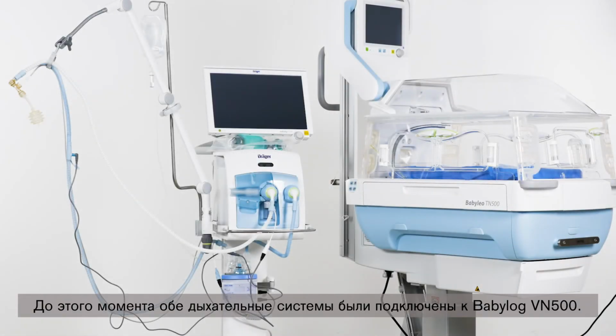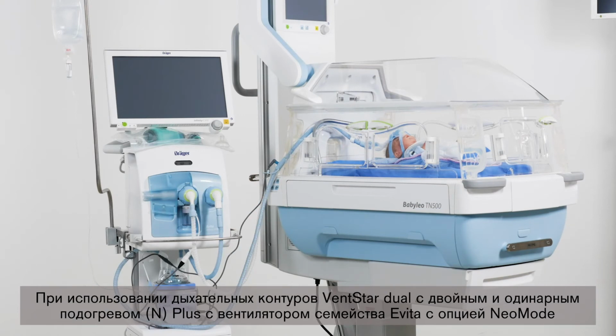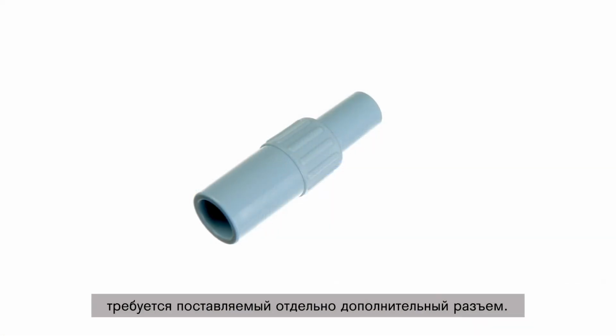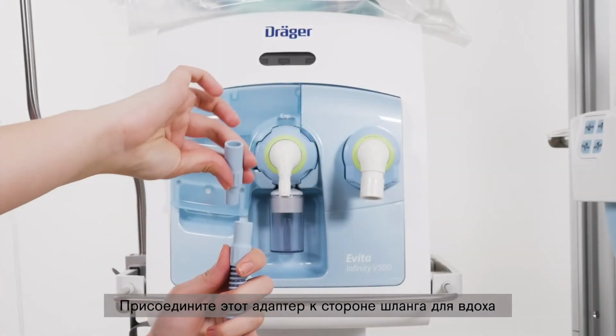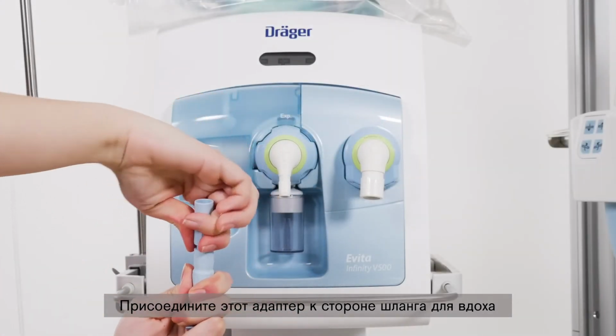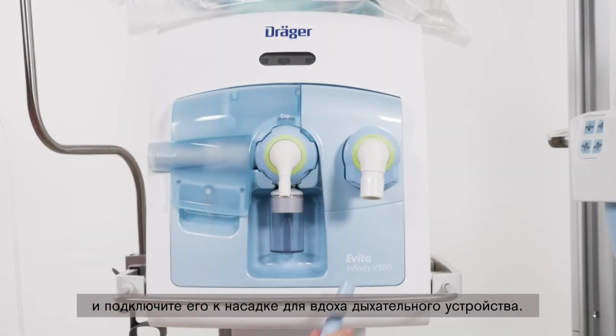Up until now, both breathing circuit systems were connected to the Babylog VN500. When using the VentStar dual and single heated N+ breathing circuits together with a ventilator of the Evita family with Neo mode option, an additional connector is required, which is available separately. Connect this adapter to the inspiratory side of the hose and connect it to the inspiratory nozzle of the breathing device.